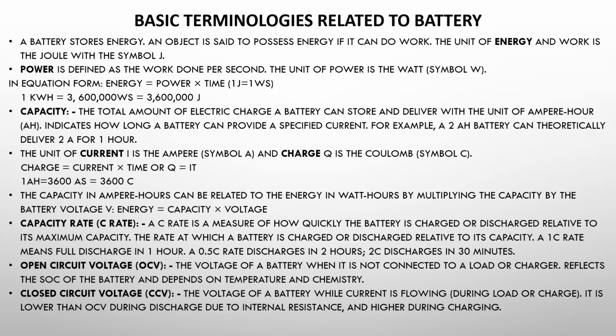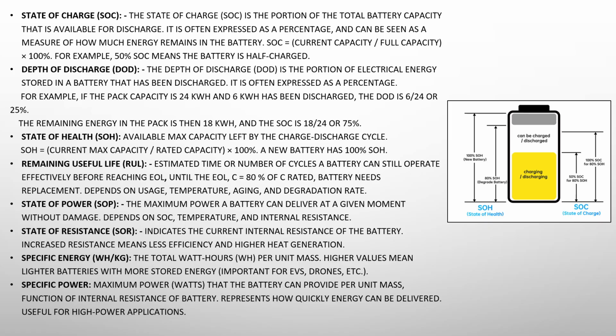So then we get to these states the BMS calculates. State of charge, SOC, is the easy one—remaining energy as a percentage, 50% SOC meaning half full. Depth of discharge, DOD, is just the opposite—how much energy you've taken out. So if you use 6 kilowatt hours from a 24 kilowatt hour pack, that's 25% DOD, which leaves you at 75% SOC. Got it—SOC and DOD are flip sides.